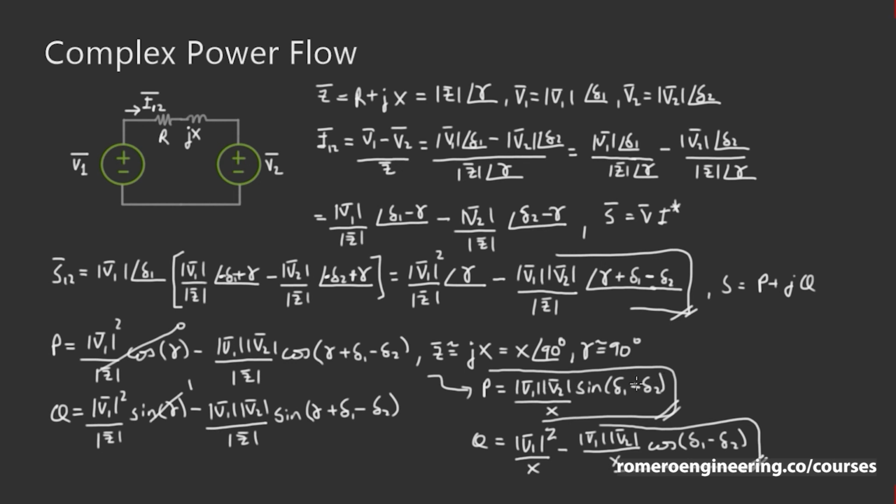And so what's done in real applications is that this angle is changed to control the power that flows through a transmission line rather than the magnitudes. So magnitudes are usually not changed. They're operated at whatever the nominal voltage is. So if this source or this generator, let's say, is rated at 13.8 kV and this generator is rated at 13.8 kV, this is typically not changed.